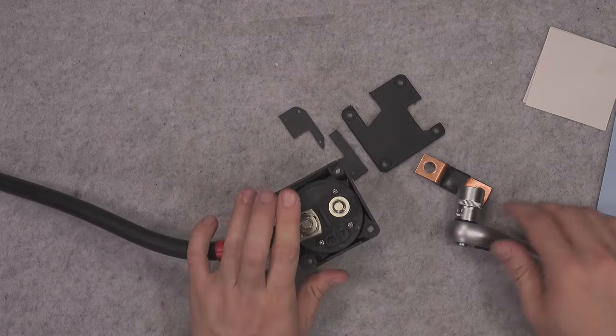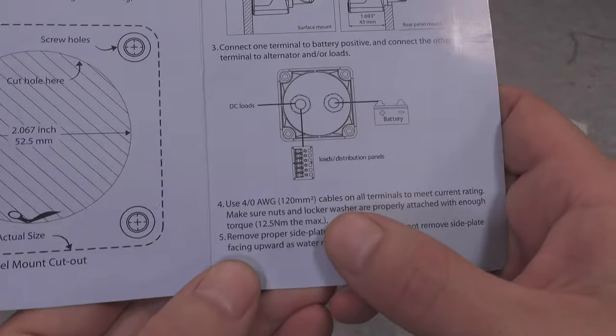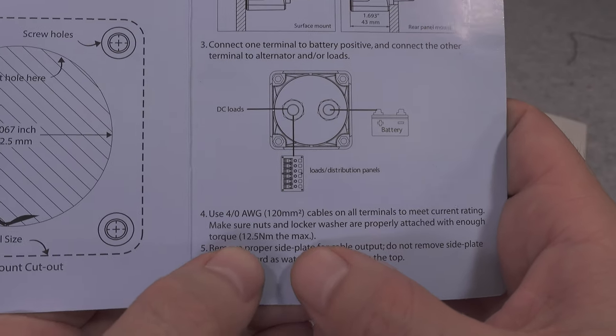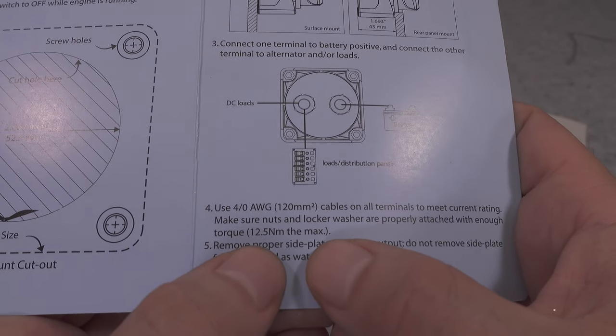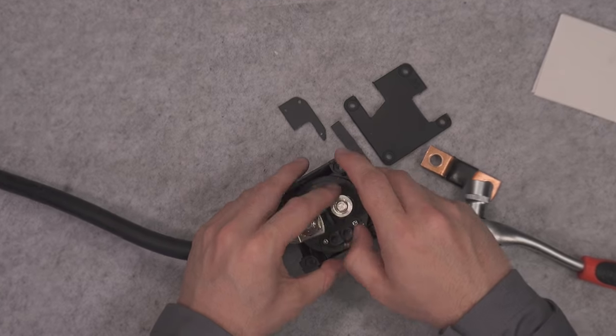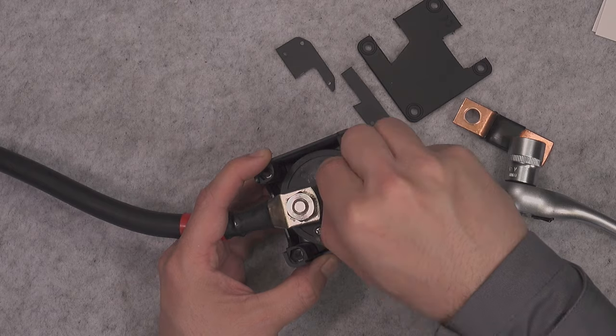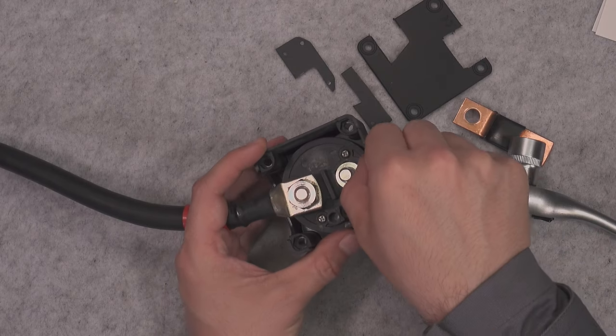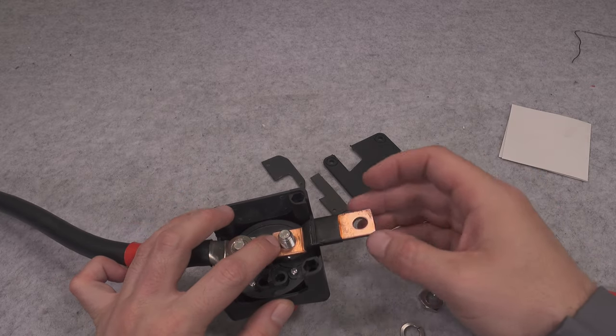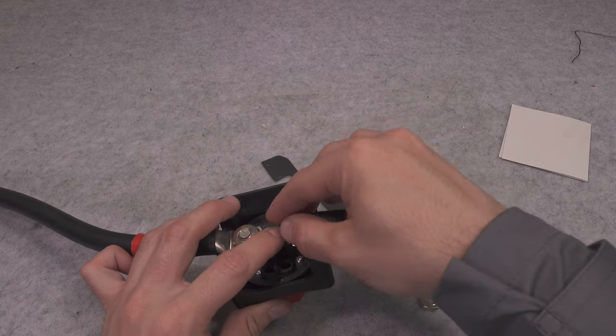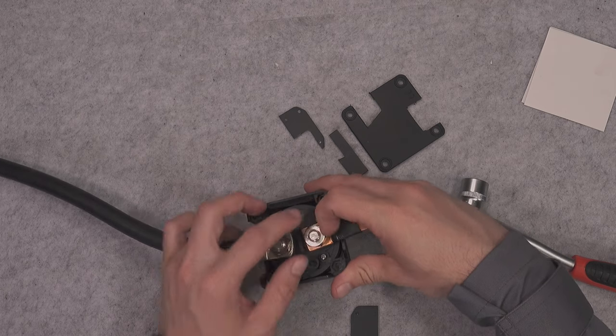In a normal mode of operation, because this is just a demonstration on my desk, we are going to be using a wrench that's got the ability to set torque. In the user manual we've got the information that we should not exceed 12.5 newton-meters. With our busbar, exactly the same situation. We can make all the arrangement. We do not have to use that output, we can just take it out and we can use that one.